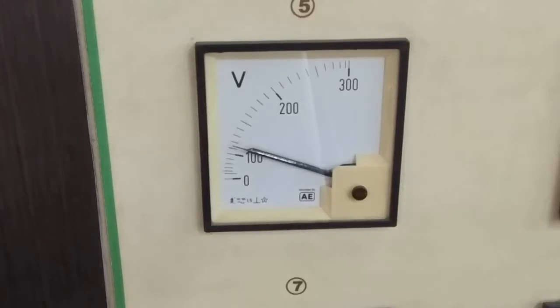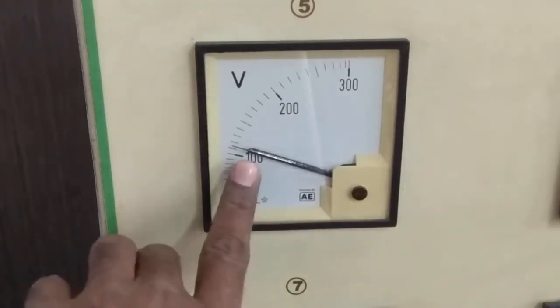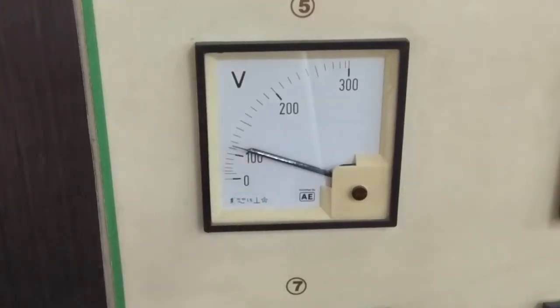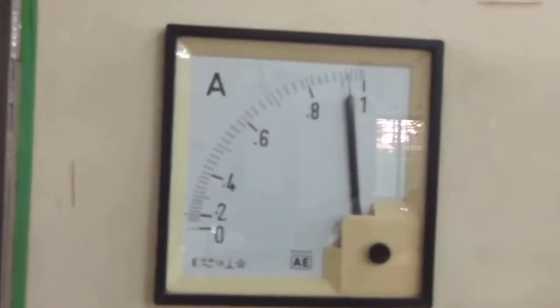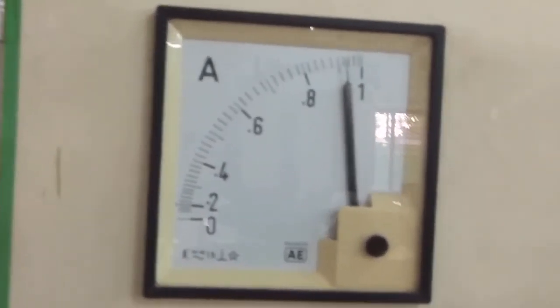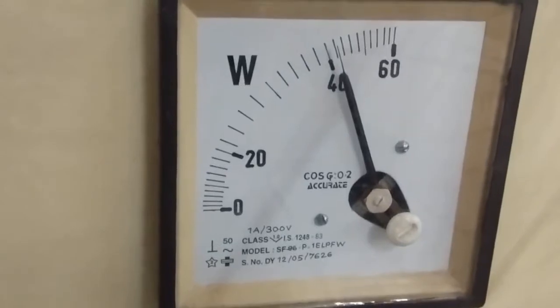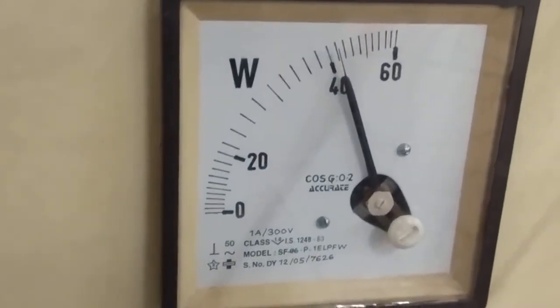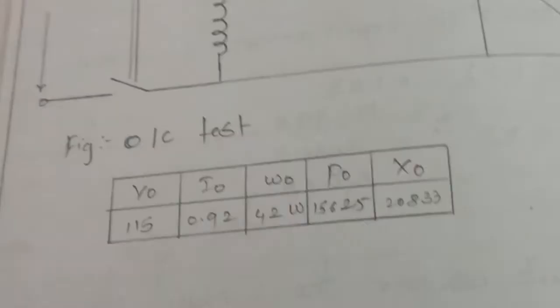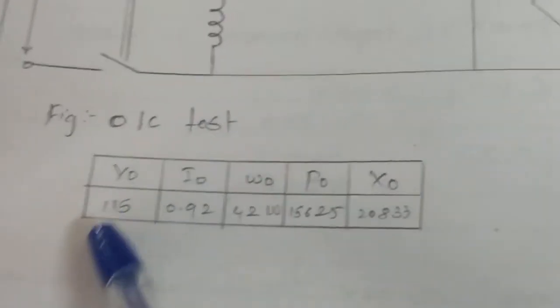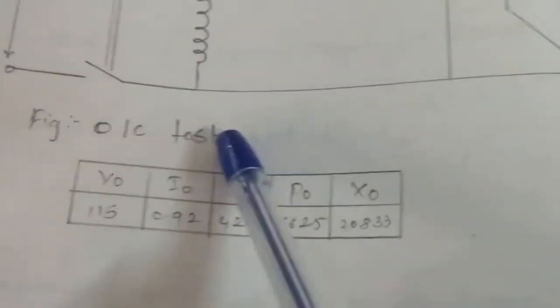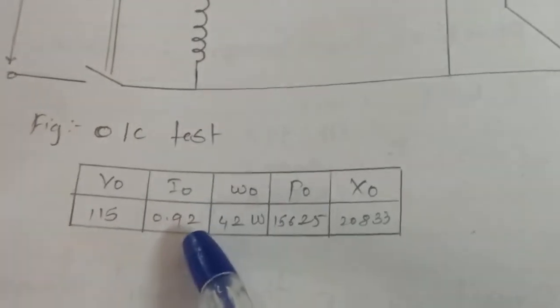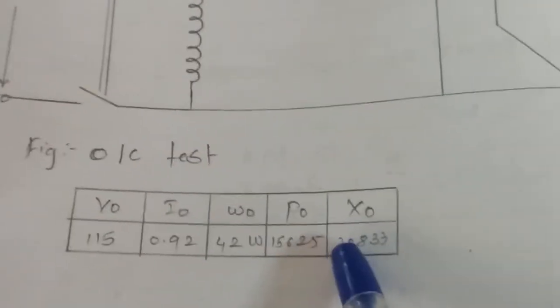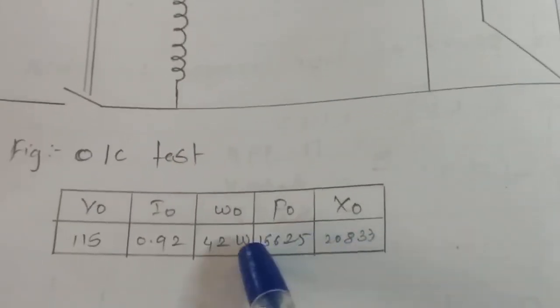You can see our voltmeter reading is 115 and ammeter reading is 0.92. At the same time, we can see the wattmeter reading is 42 watt. We will note down all these readings in the observation table for the OC test: V0 is 115, I0 is 0.92, W0 is 42 watt. And R0 and X0 we will calculate, and after doing the calculation we will note down the reading here.